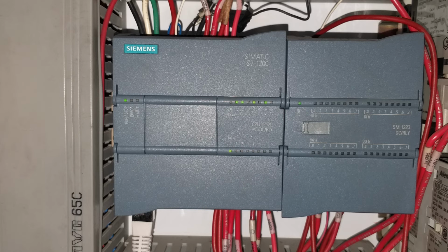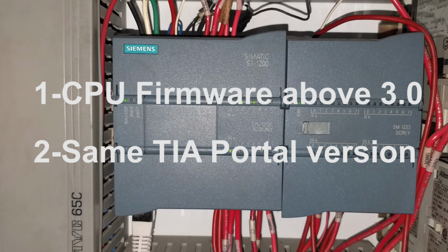In today's session, we will see how we can take a backup of S7 1200 or S7 1500 PLC. Before taking the backup of any S7 1200 or 1500 PLC, there are two things which we have to consider. The first thing is that the firmware of the CPU should be above 3.0. If it is less than 3.0, then we cannot take its backup.